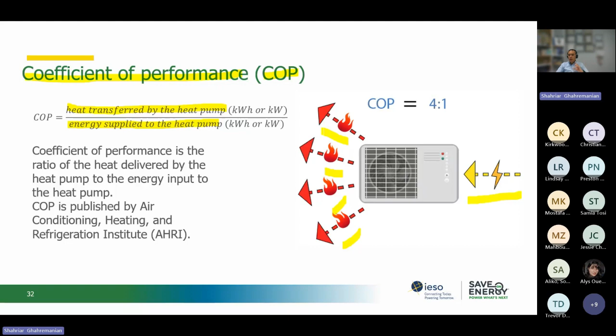But again, all the manufacturers have to report this one. The next performance terminology for the heat pumps is the energy efficiency ratio, or EER. This is just for the cooling capacity of the heat pump. Basically, it tells us if we move cooling, which means that we remove heat from inside of our building to outside, divided by the amount of electricity provided, how much is that efficiency? So EER is just providing the cooling output, or the cooling efficiency, of a heat pump.